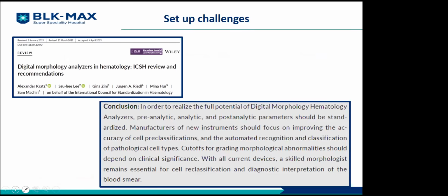Now, when you set up any instrument in your setup, there are challenges. Anything new which comes in, you need to get used to it, and the entire process needs to be set, standardized, and moved across. So when you have setting up challenges, what do you do in such circumstances? As far as the digital morphology platforms are concerned, fortunately, there is certain literature available, the ICSH, the International Council for Standardization in Hematology recommendations, wherein they have talked about how the digital morphology analyzers need to be set up in hematology and eventually taken care of with respect to the morphological information which comes out from them.